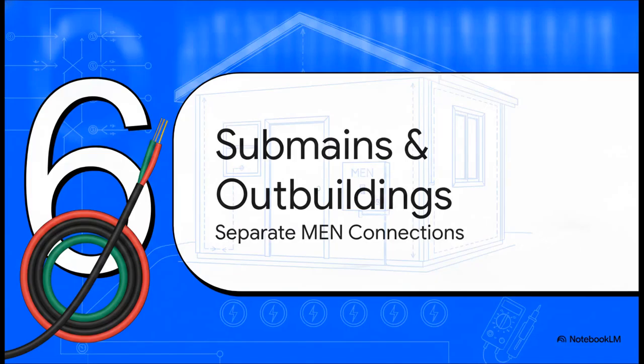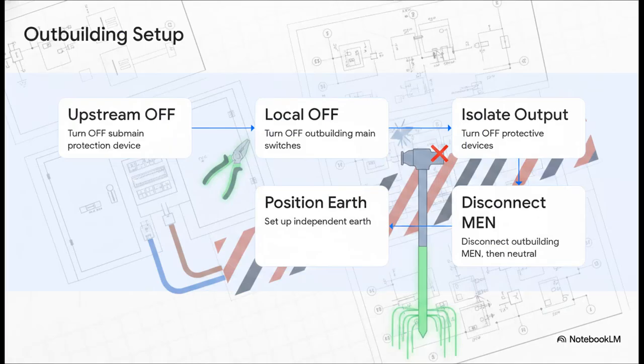Section 6. Submains and Outbuilding Tests. When you're dealing with a separate outbuilding that incorporates its very own MEN connection, the testing approach requires some vital adaptations. The big, critical difference here is dual isolation. We have to start upstream at the main switchboard and turn off the submain protection device. Then, we literally walk down to the outbuilding and turn off the main switches and protective devices locally. Only after ensuring total physical isolation across both boards do you disconnect the outbuilding MEN, then the submain neutral, and set up your independent earth.